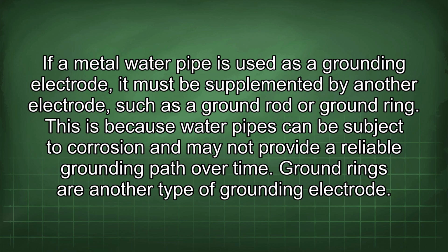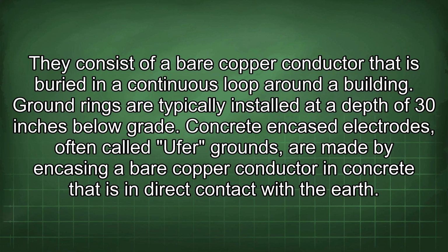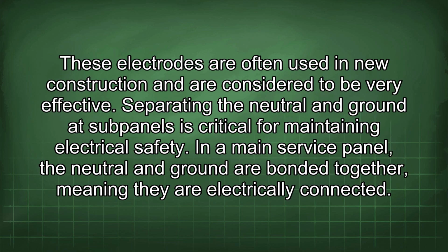Ground rings are another type of grounding electrode. They consist of a bare copper conductor that is buried in a continuous loop around a building. Ground rings are typically installed at a depth of 30 inches below grade. Concrete encased electrodes, often called Ufer grounds, are made by encasing a bare copper conductor in concrete that is in direct contact with the earth. These electrodes are often used in new construction and are considered to be very effective.